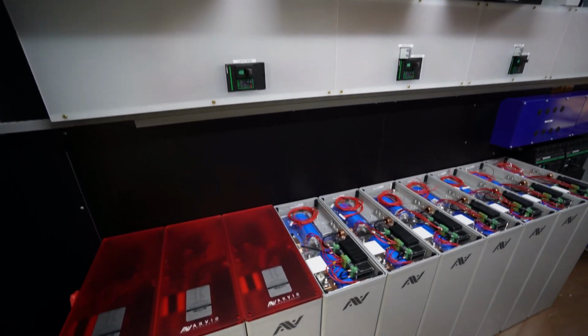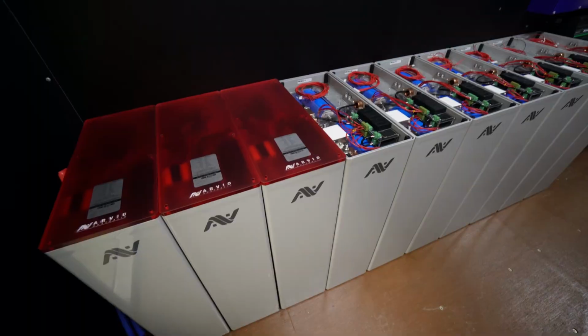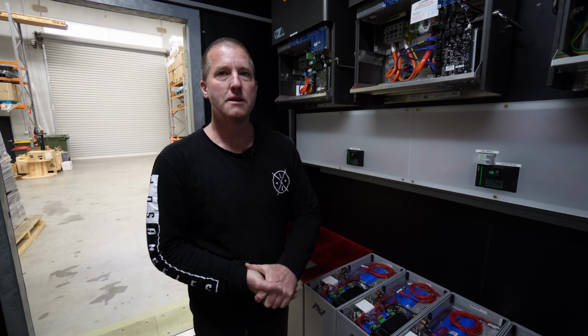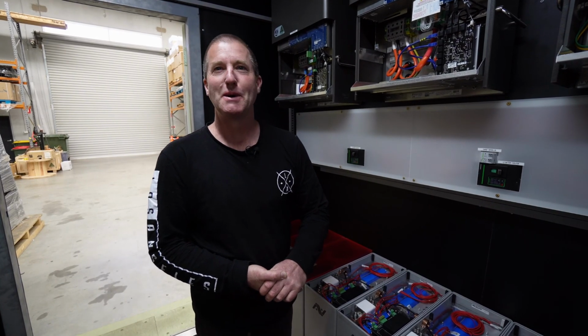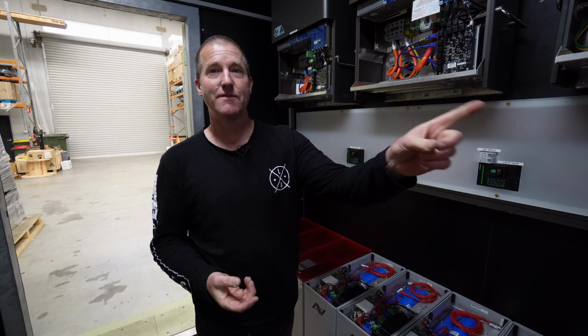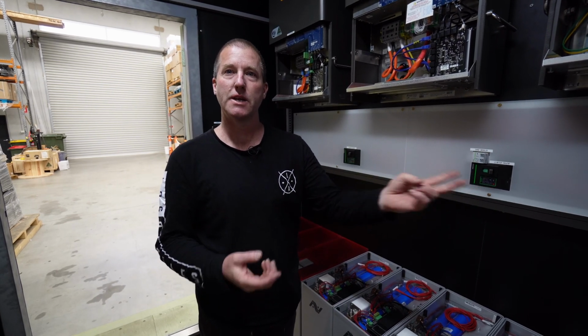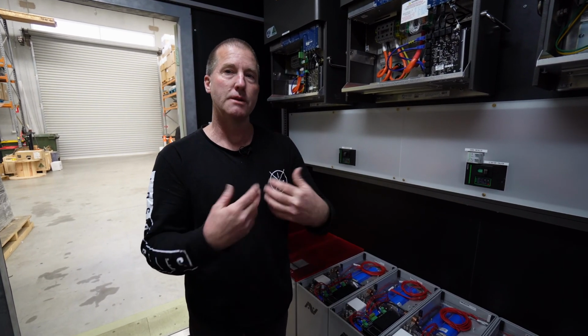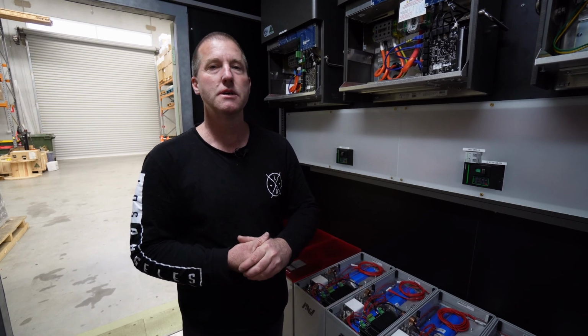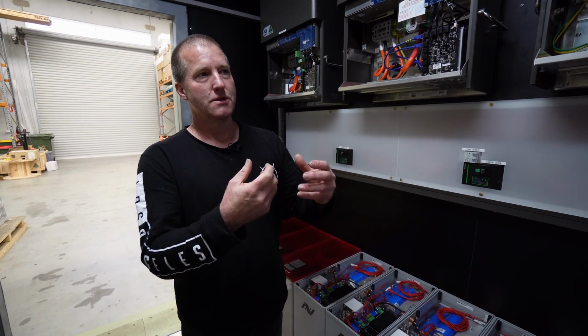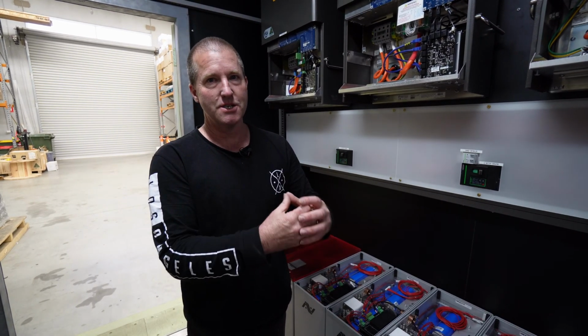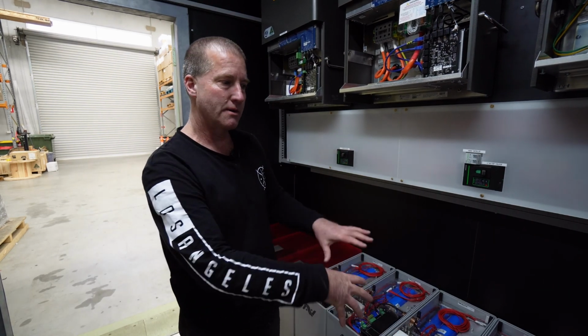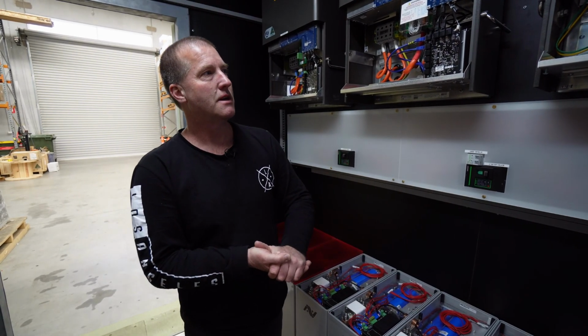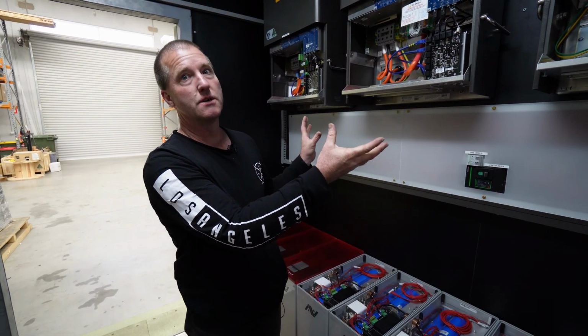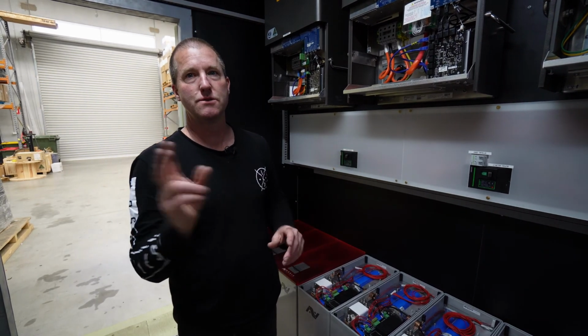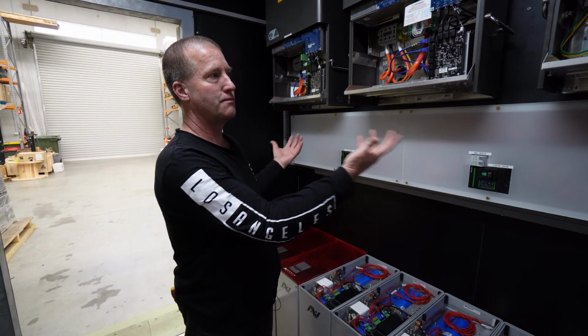Right, so the customer had two-phase, you're giving them three-phase and more capacity. We're actually giving them five-phase power - phase A and phase B, which are the two SWER line phases, 180 degrees apart, returned to them as usable AC supplies. We're using those two inverters to charge a DC bus and our own battery bank here, which we'll show you in a moment, and then reforming three-phase on site. So we have 5 different phases on site: 2 single phases they can use, and a pure three-phase solution.